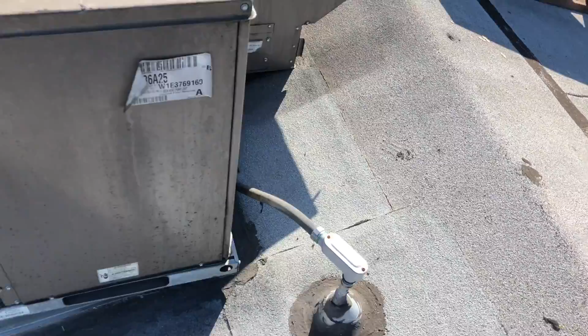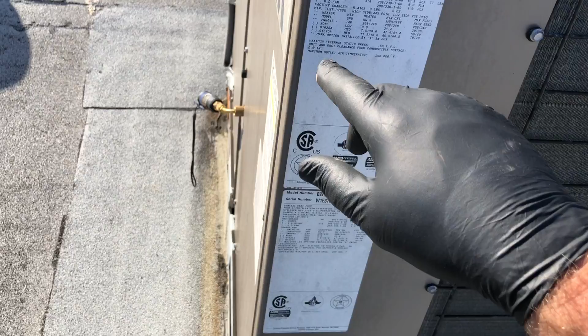3 tons, a little small for that store. All the heat load that's in there too, I can tell you that. For the square footage, if it was just human occupancy, 3 ton would probably be okay, but with the heat load, with all the equipment and stuff, not a chance.